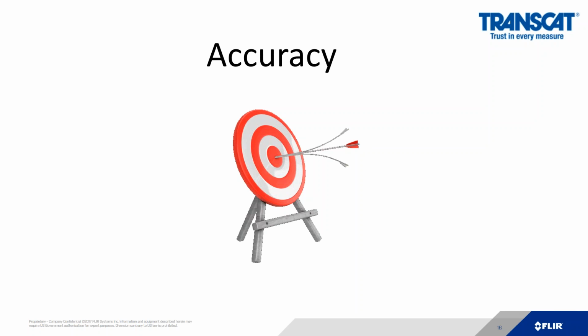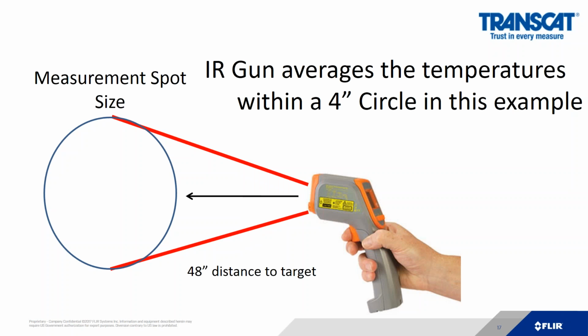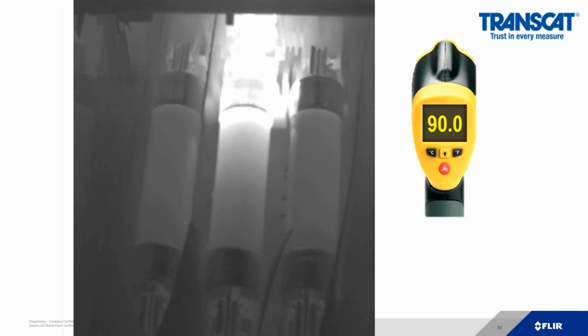We're now going to talk about accuracy. Now, everyone who's had a spot gun, hopefully you've looked on the side of it, because on the side of it, the spot gun tells you its spot size ratio. Now, the problem with a spot size ratio is it's hard to understand what that practically means. So if you have a 12-to-1 spot size and you are 4 feet away or 48 inches away, your measurement area is 4 inches. Now, that may not seem like a big number, but trust me, it is when you start looking at your targets.